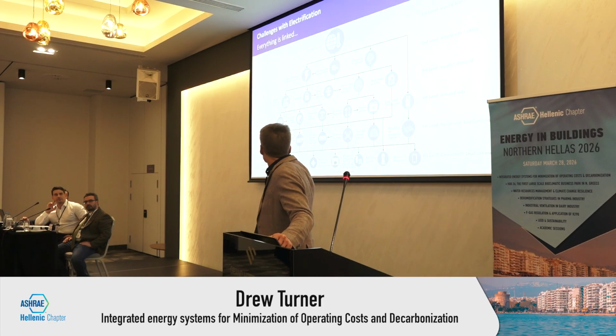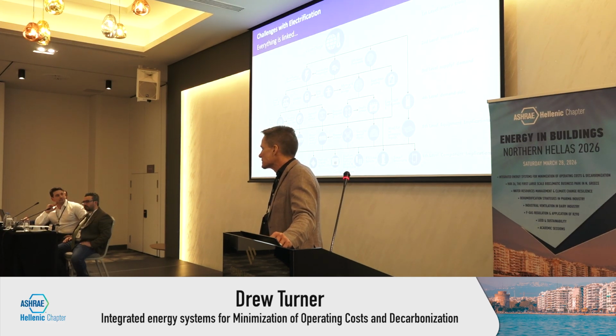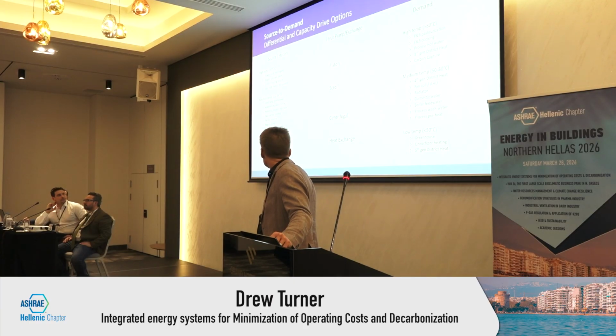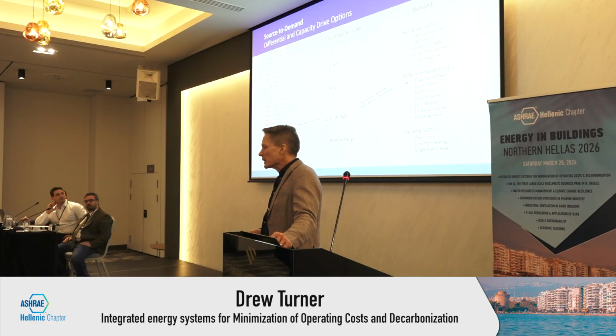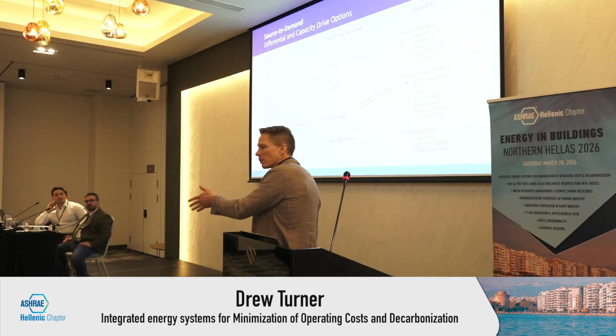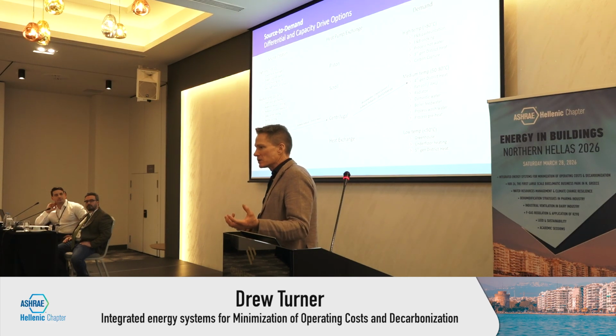You can see a flow down from first level macro trend down to the demand side, and then ultimately to what my colleagues like, the component implications, what we need to work on next in terms of components. You can see a trend of what's driving what's needed from a technology standpoint and systems. So these are a few examples. Every time we work on a system like this, we try to summarize it based on source, demand, and then heat pump. When you're evaluating whether it's going to make sense to recover heat from an industrial process to replace the boilers that are heating that facility, the source temperature and demand temperature and capacity and simultaneous operation are what are most critical to that payback, to that analysis of whether or not that retrofit's going to make sense.